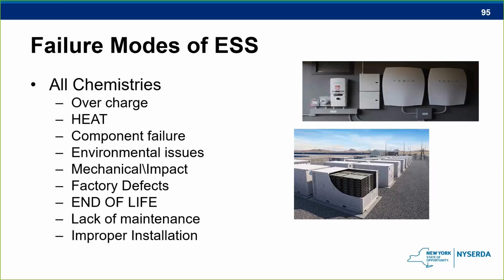So some of the failure modes that you see here on this slide is the overcharge, and we've seen that before on lead acid batteries. I've been to a couple of them in telecom communications or UPS systems. So usually if we shut them down, they should be all right. But that was a big one that we wanted to know a little bit about.